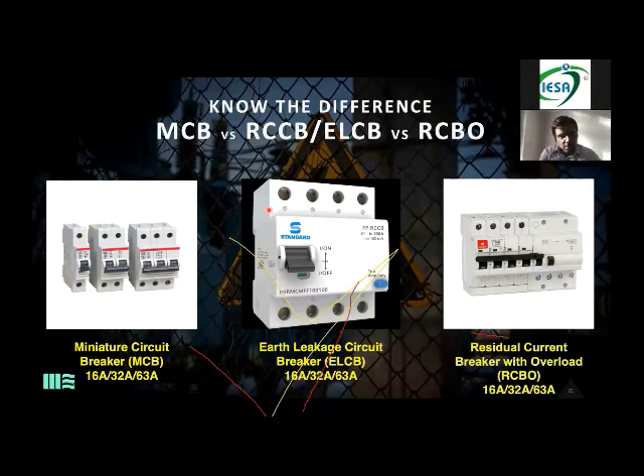For an ELCB, there is an overhead test regularly. Over here, you see that on the ELCB there is a test button, so you can check whether it is getting tripped or not. For an MCB, if you have a small load, what we normally do in our warehouse is we have small load banks which we have created for 10 kilowatts, 20, 30, and it goes up to 200.